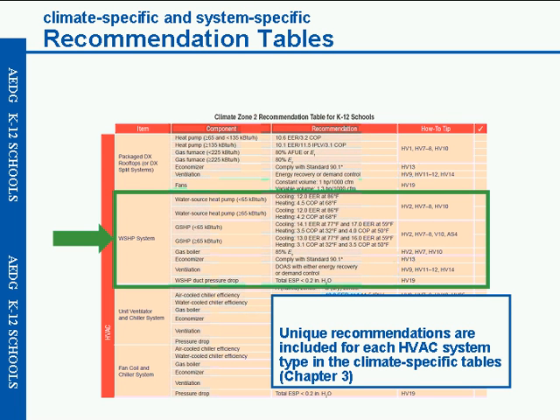Here's an example of the recommendation table for the K-12 schools, and you can see that the different HVAC types are listed in the first column. Under each one of those, it has unique recommendations for each HVAC system. There's one of these tables for each of the different climate zones. This particular table is from climate zone 2, and the highlighted area would be for a water source heat pump, showing the different sizes of the components, as well as the recommendations in terms of COPs and EERs, and then finally the how-to tips, showing where you can go for more information about each of these pieces.